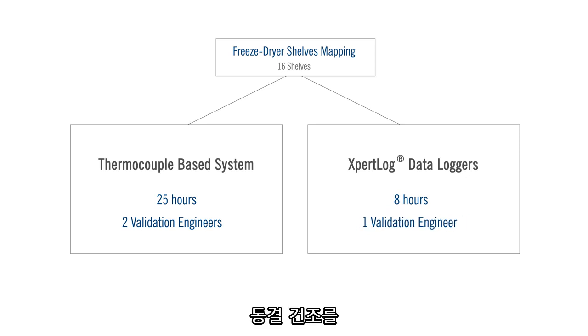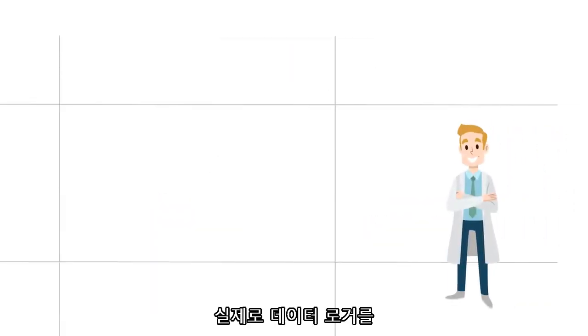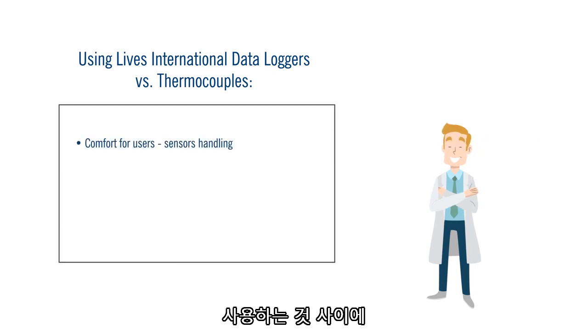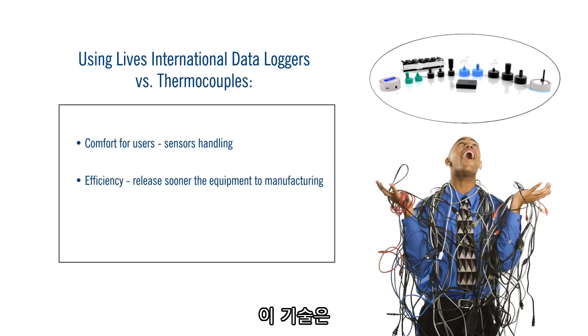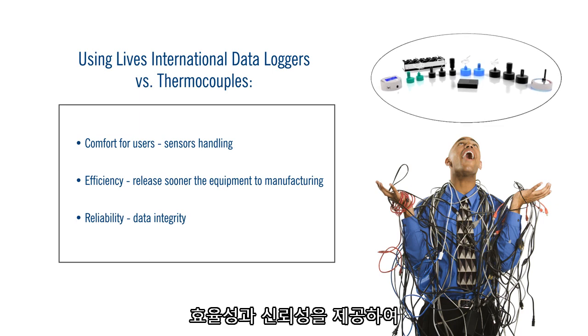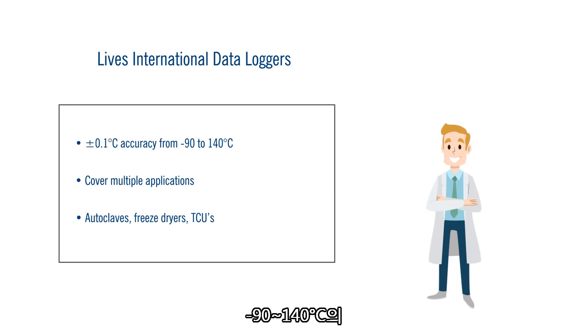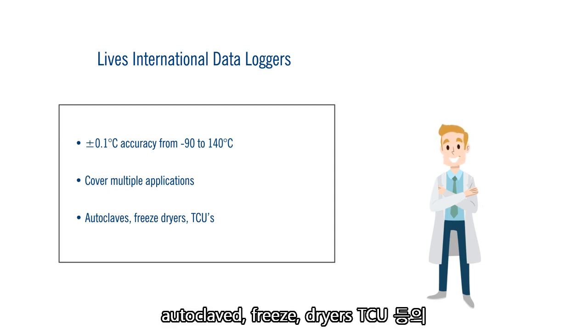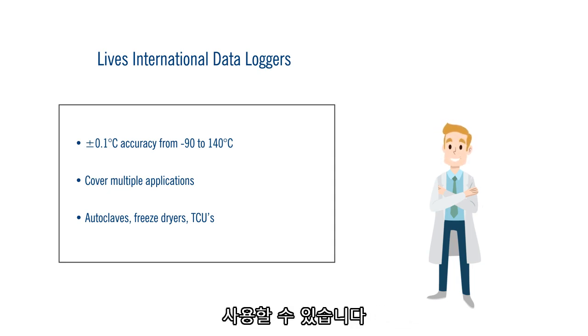A significant difference can be observed between using thermocouples versus Lives data loggers to run a freeze-dryer shelves mapping. It is obvious that new technologies bring more than comfort for the user. They bring efficiency and reliability, making old technologies obsolete. Lives International real-time wireless data loggers offer an impressive plus or minus 0.1 degrees Celsius accuracy on the whole range of temperature from -90 to 140 degrees Celsius, and they can be used to cover multiple applications such as autoclaves, freeze dryers, TCUs, and so on.